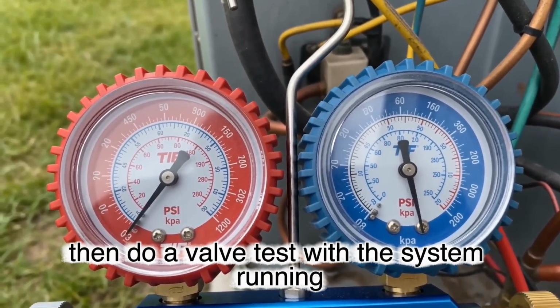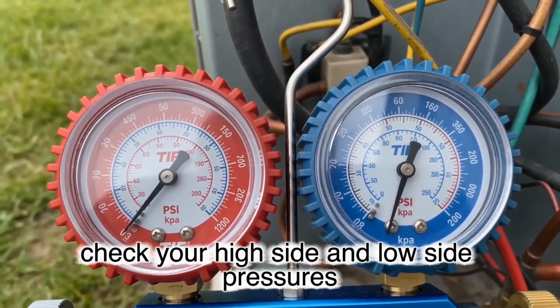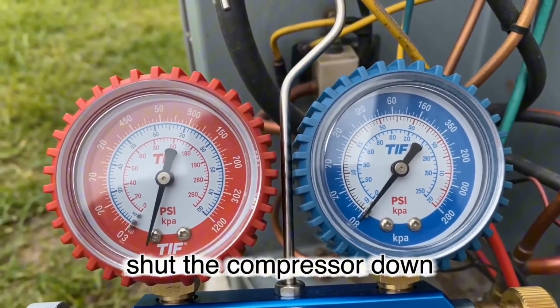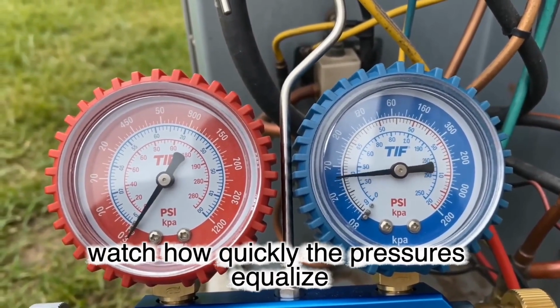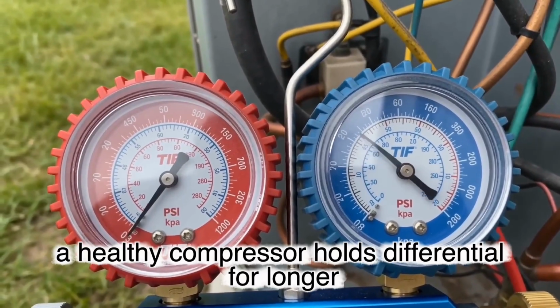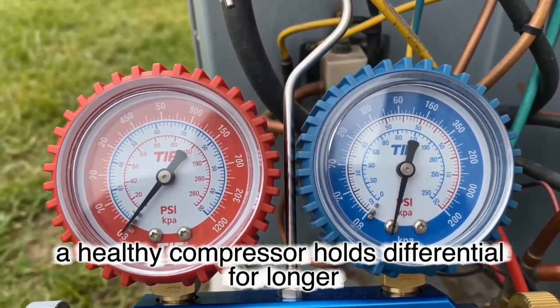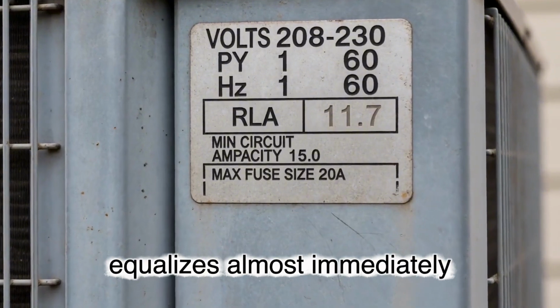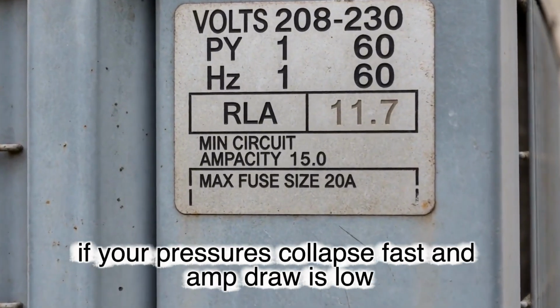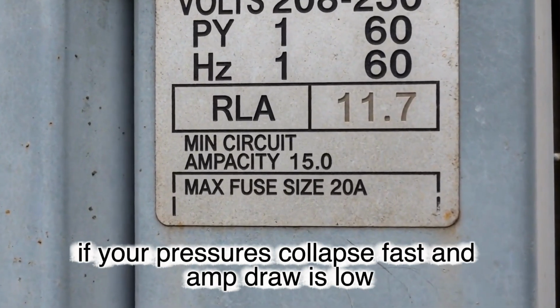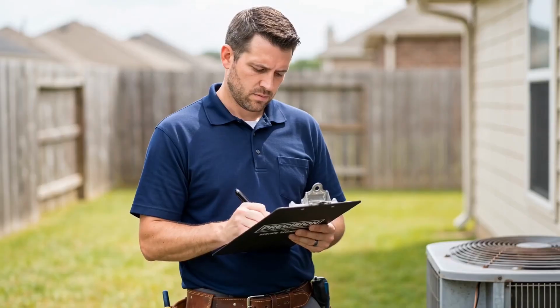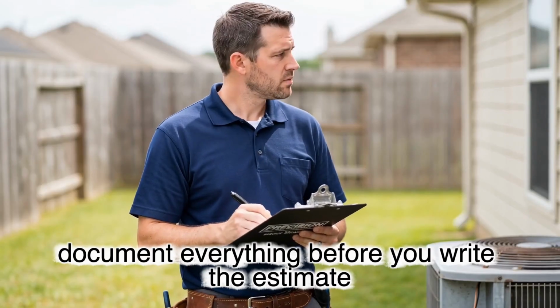Then do a valve test. With the system running, check your high side and low side pressures. Shut the compressor down. Watch how quickly the pressures equalize. A healthy compressor holds differential for longer. A compressor with blown valves equalizes almost immediately. If your pressures collapse fast and amp draw is low, you have compressor valve failure. Document everything before you write the estimate.